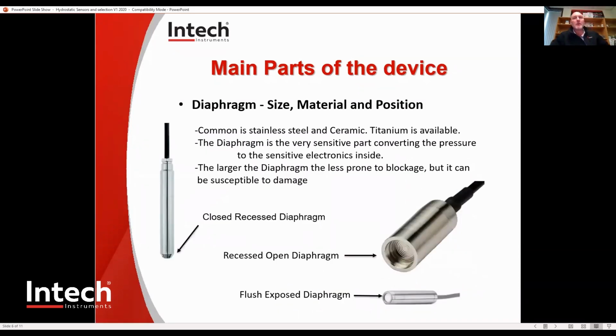The next part that we need to consider is the diaphragm. Now, common is stainless steel and ceramic, and less common is titanium. This is the most sensitive part that transfers the medium pressure to an electronic analog signal, as damage to the main part will cause the unit to be damaged. That's why it's very, very important never to touch the diaphragm with a finger or any tool. Even if it's dirty, you'd be better off to clean it under gentle running water or chemicals that are compatible with the diaphragm material.